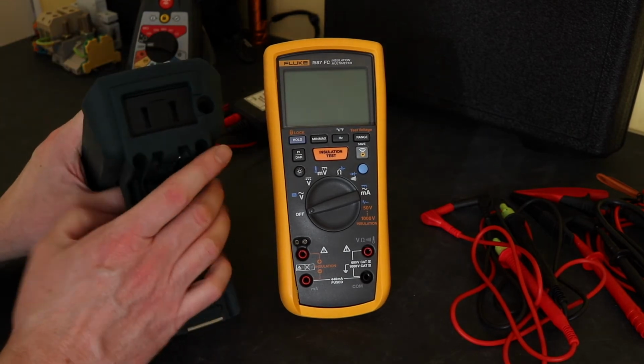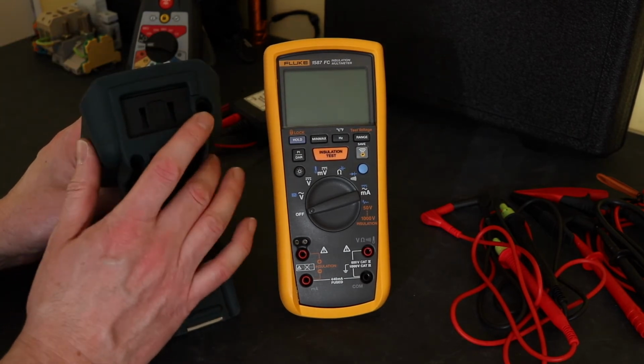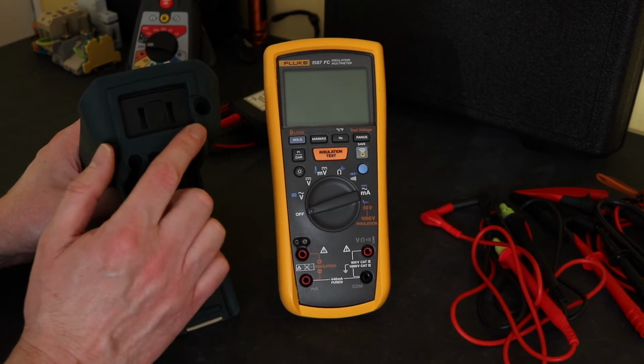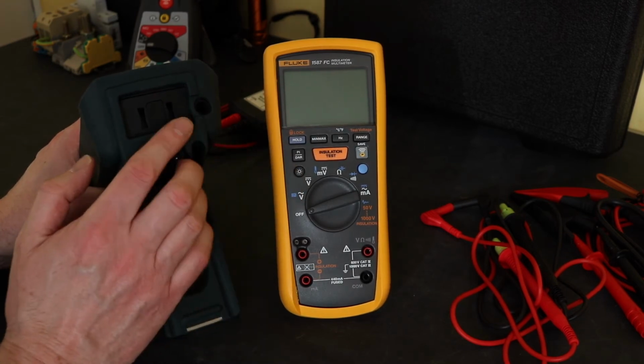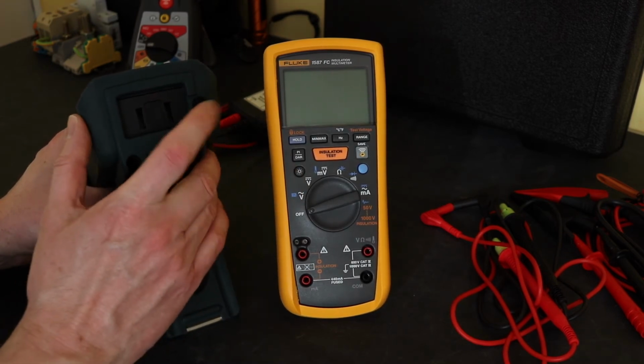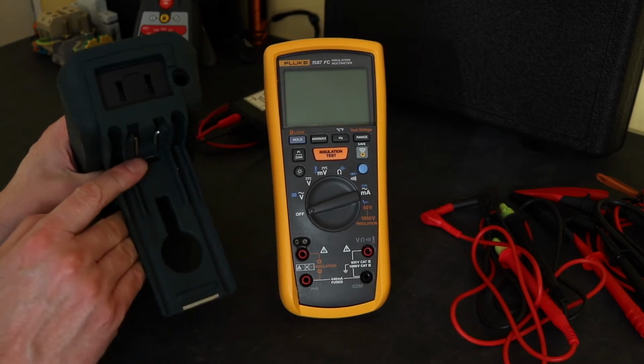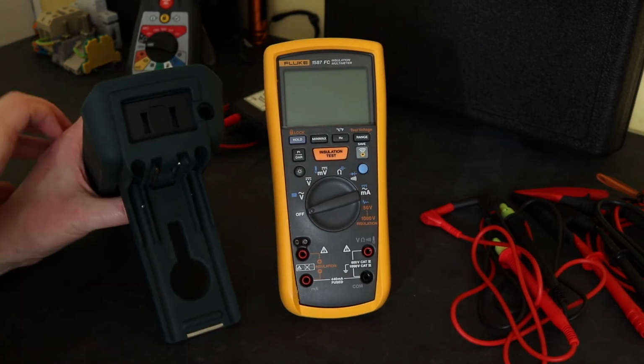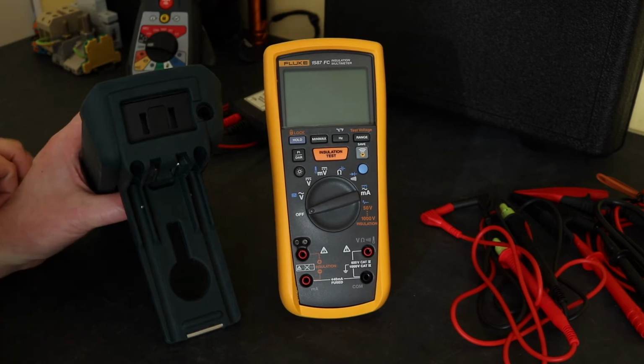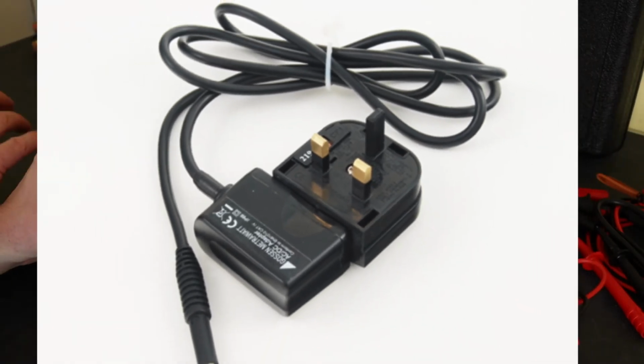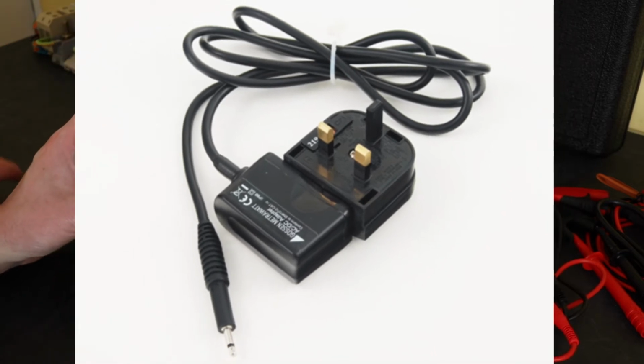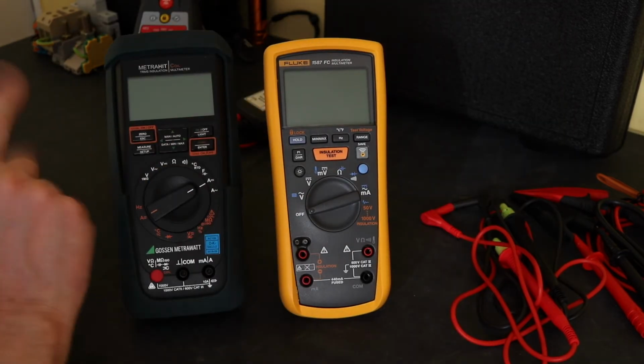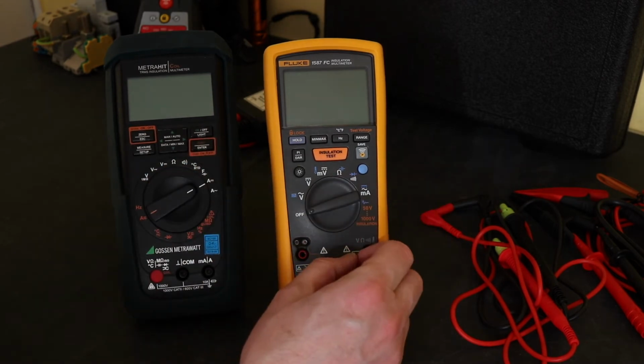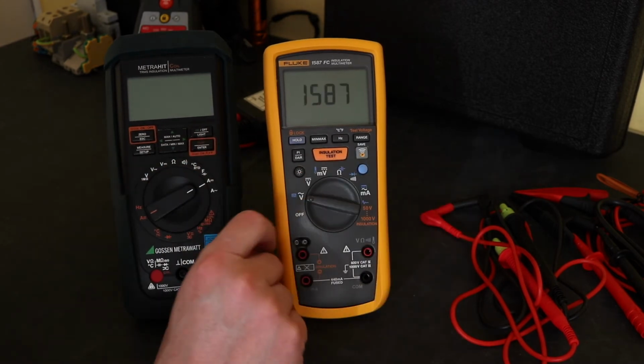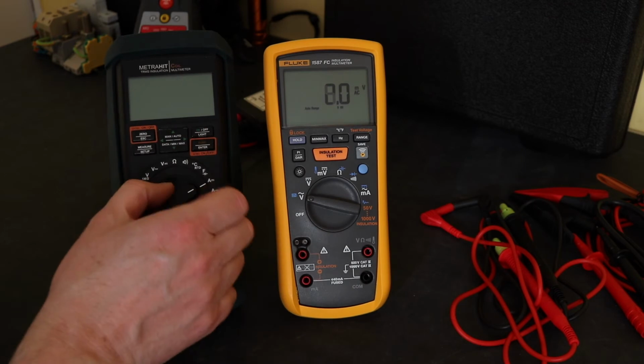One extra additional bit to the Gossen Metrawatt is you can power this from a mains adapter, which you can't do with the Fluke. So if you're doing some long-term logging, you've got that option there to save on battery power. And that PSU does not come as part of the kit, but it is an optional extra at a cost of £143. With regard to the actual instrument operations and functions, we've got volts AC on this.